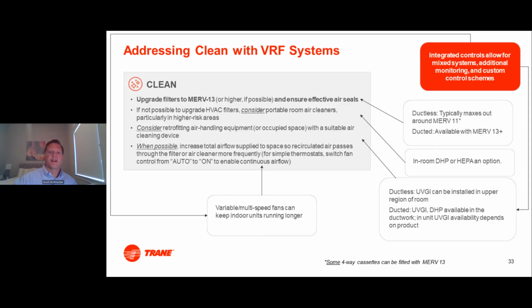Last but not least, I want to address the clean pillar. So how do we take the bad stuff out of the air? Core recommendation from ASHRAE and CDC is to provide at minimum MERV 13 filters or higher if possible. And then we want to ensure we have air seals. If that's not possible, then we want to look at potentially putting in portable air cleaners in the room, certainly for higher risk areas. We could consider things like retrofitting air handling equipment with suitable air cleaning devices like UV lights or other technologies. And there obviously is commentary that when possible, we want to increase the total airflow supplied to the space so that we get more air flowing through the filter.